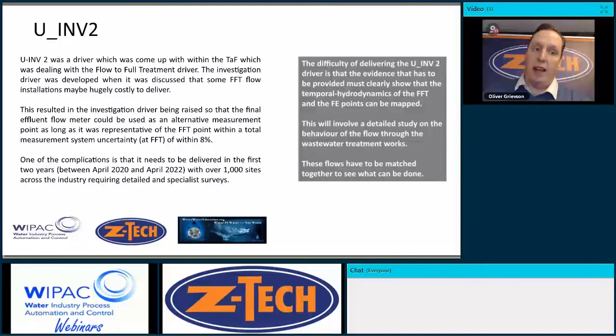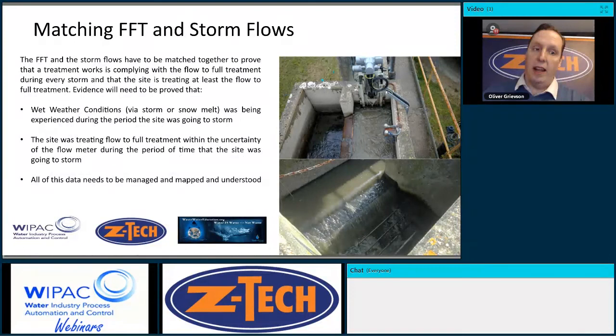Now, it may look very small, it may look rudimentary, but guess what? That top flow measurement device is designed to Formula A. So with a process engineering hat on, I can very confidently say that that works will always pass forward FFT. It will always comply. So to install a flow measurement device in that particular works is, in some ways, nonsensical, but it's going to come with a very large bill. And that's, of course, where the U_INV2 driver comes in.